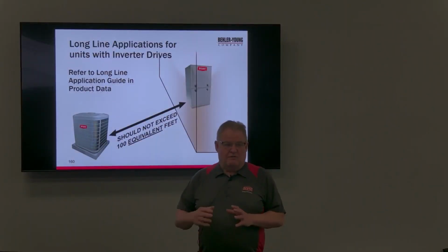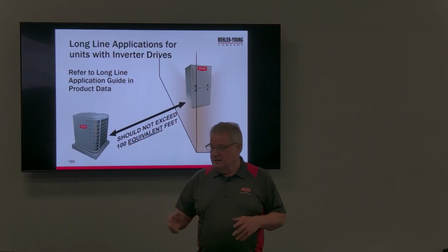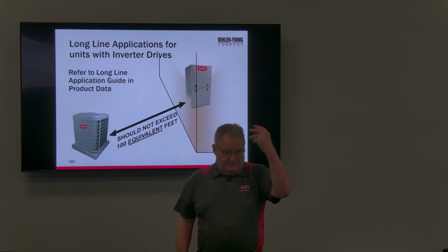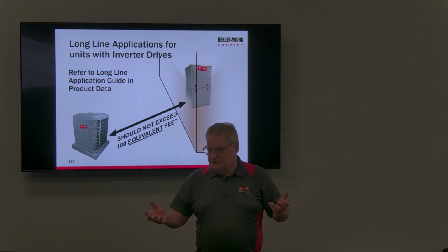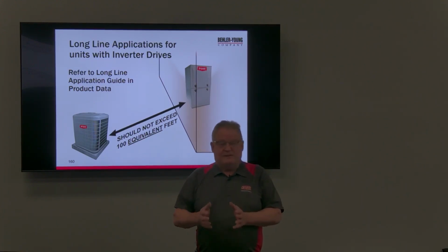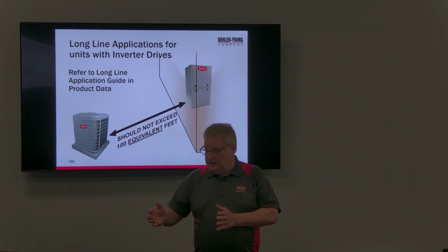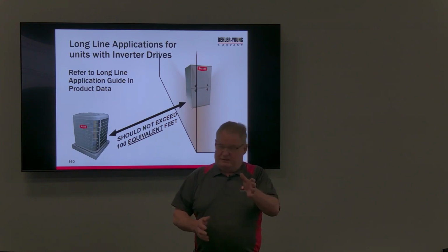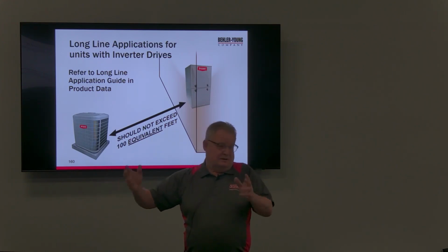So if you're going over 50 feet, right? You look in the book, says I need 5/8, 3/8 line set. You start going over 50 feet, you want to go into the long line guide and see what you might have to do. Because it may have you upsize the suction line, or it might just tell you I'm going to lose 1% capacity if I do this. Okay, is that okay?